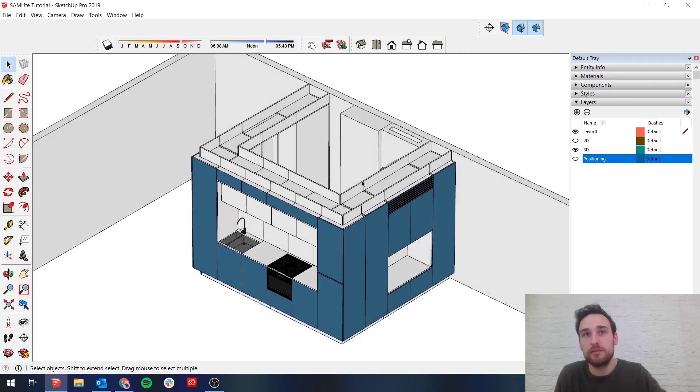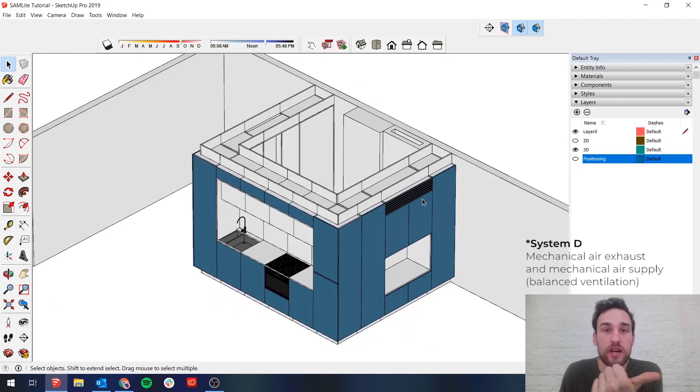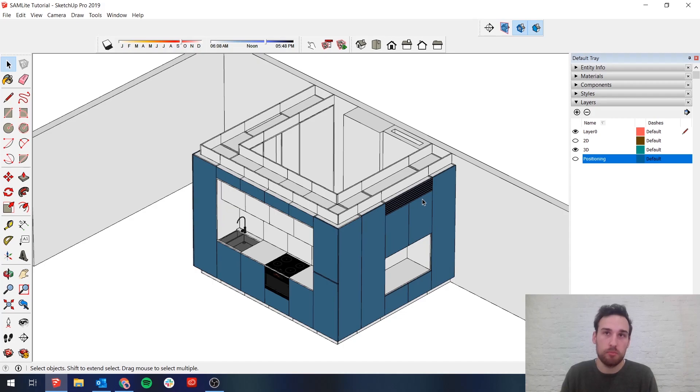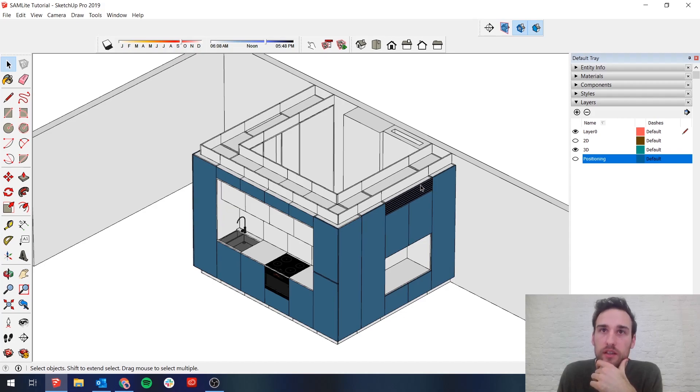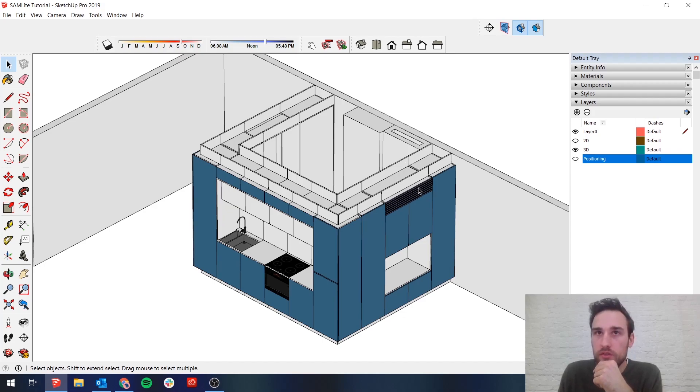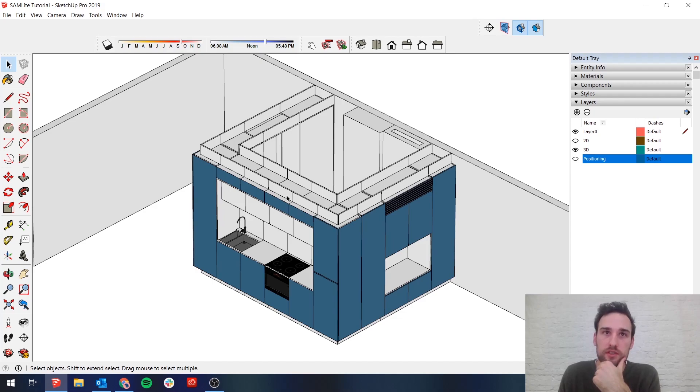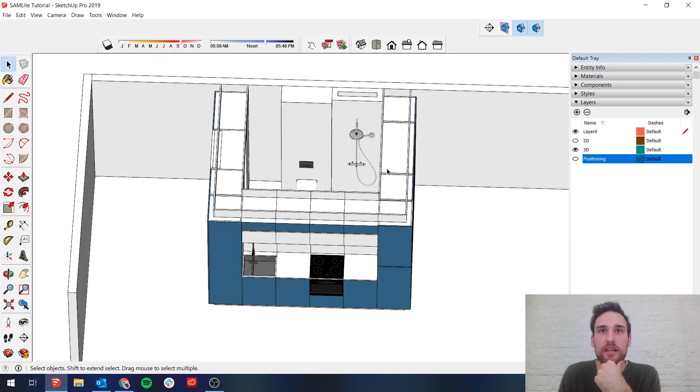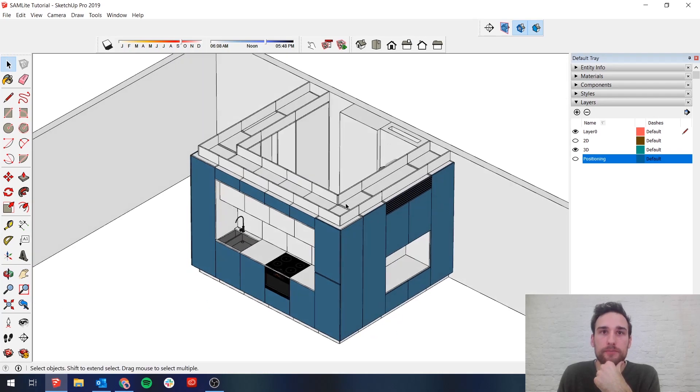And if you have a system D, you will have both extraction points and inflow points. So the influx of fresh air will be where we place our convector so it gets blown through the heating element into the living space and obviously the extraction points will be kept in the same positions above here in the extraction fan and near the shower.